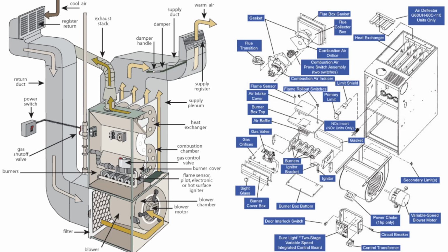Some of them will have a sill panel with a sight glass so that you can look into the burners with a safety factor. But I do recommend this. Anytime you are working on your furnace or doing any kind of inspection on your furnace and it is running live and you've pulled the door panel and you're engaging the safety switch, make sure you're wearing safety glasses. You don't want something to happen and then you lose your eyesight due to a mishap. Make sure you take every safety precaution that you have.